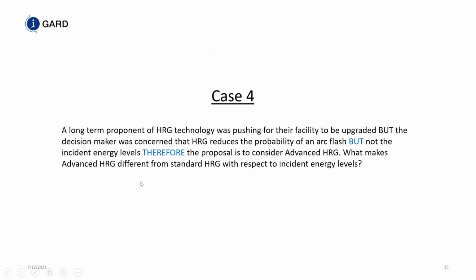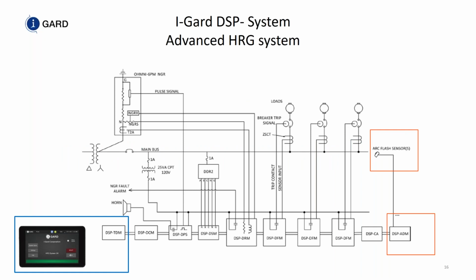So case number 4, a long-term proponent of high resistance ground technology was pushing for the facility to be upgraded, but the decision maker was concerned that high resistance grounding reduces the probability of an arc flash, but not the incident energy or severity of an arc flash. So they approached us and wanted to use our advanced HRG high resistance grounding system to both lower the probability as well as the magnitude.